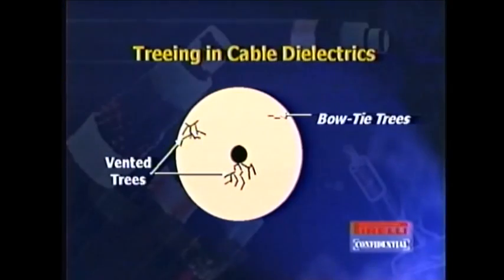We'd like to have an ideal extrusion process with medium voltage cables, but unfortunately that's not always the case. Bow tie trees in and of themselves are not huge problems as long as they're fairly small and there's not a high density of them. However, if they get very large and there are a lot of them, it can be a problem over time. The ones we really have to watch out for, though, are vented trees.